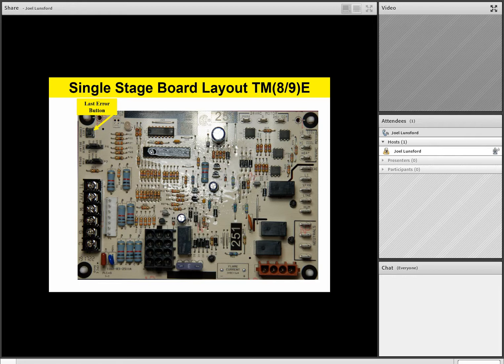Now it should be noted, if you hold that last error button down for about 10 to 15 seconds, it'll reset the memory back to 0. Or if you depress it, you can push it and start retrieving the last 5 errors as well. So the last error button is a convenient way for the technician to find out what's going on with the board, if it's had some previous errors, and then to reset the error memory if so desired.